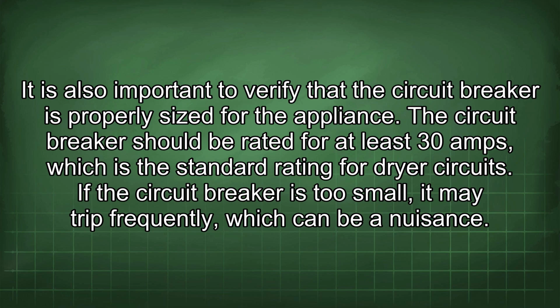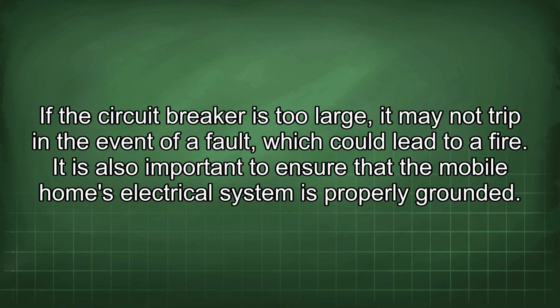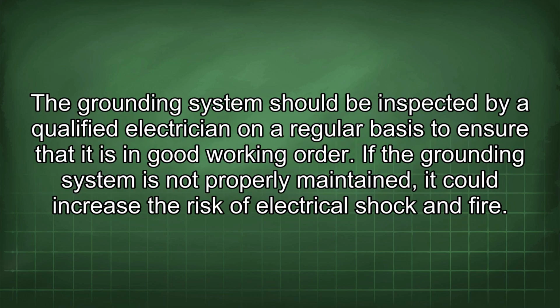If the circuit breaker is too small, it may trip frequently, which can be a nuisance. If the circuit breaker is too large, it may not trip in the event of a fault, which could lead to a fire. It is also important to ensure that the mobile home's electrical system is properly grounded. The grounding system should be inspected by a qualified electrician on a regular basis to ensure that it is in good working order.